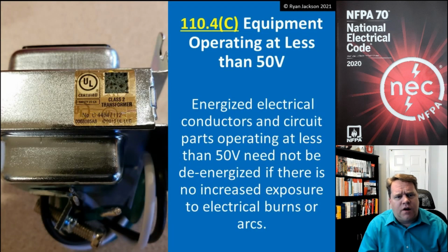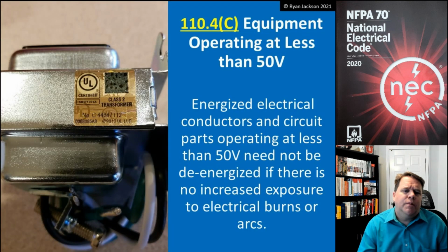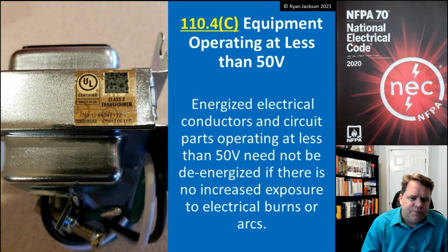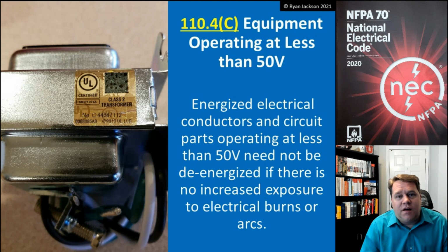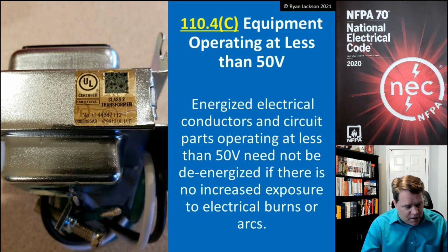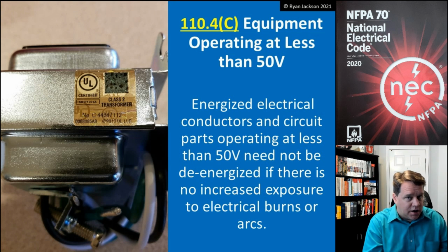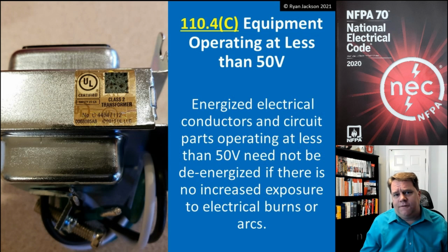The other times that I can work energized is for equipment operating at less than 50 volts. Energized electrical conductors and circuit parts operating at less than 50 volts need not be de-energized if there's no increased exposure to electrical burns or arcs. Okay, now, when it comes to shock, that's driven by voltage. So less than 50 volts, we're good as far as the shock is concerned.